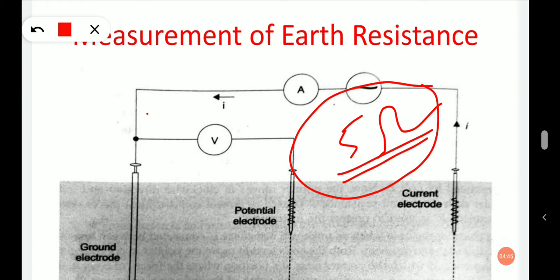There are several factors upon which the resistance of grounding system depends, which are the depth of electrodes buried under the ground, the specific resistance of the soil around the electrode, which varies for the different type of soil and moisture level in the soil, which in turn varies the electrode resistance, and the material used in manufacturing of electrodes and their shape.